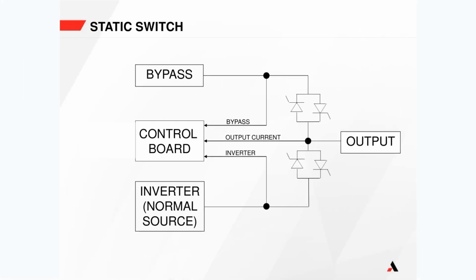So what Jeff is asking is, if this control board power supply fails, but we still have bypass available, the inverter control boards are going to fail. So what's going to happen is we want the bypass static switch to come on. But if we don't have any control power to tell the SCRs to come on, then we would be dead in the water, as most people would say.